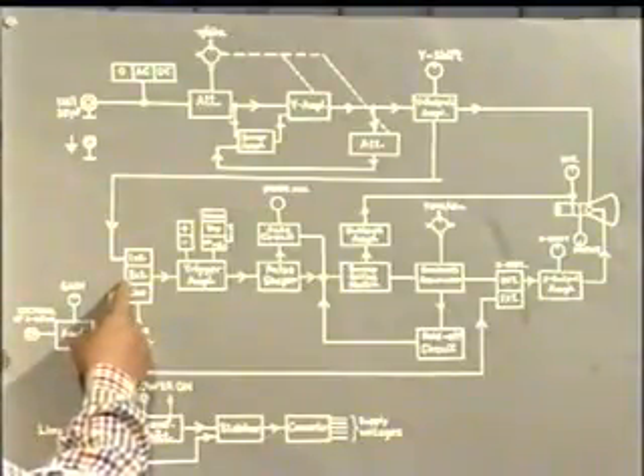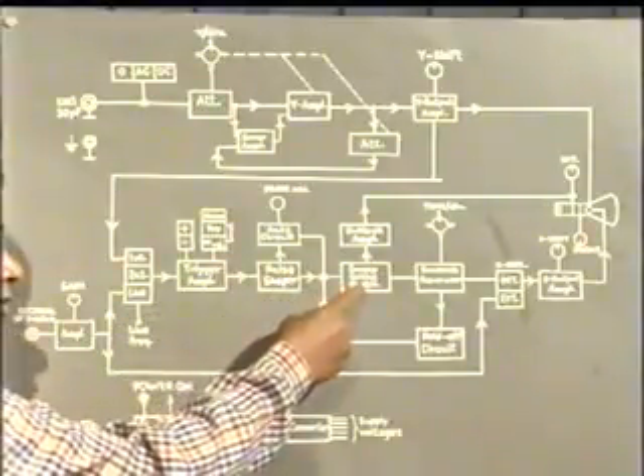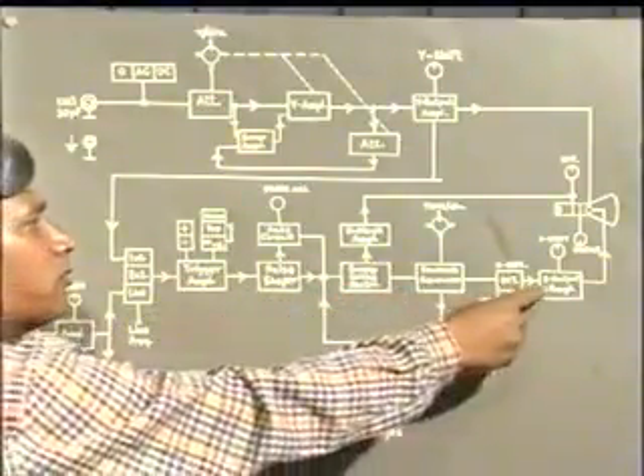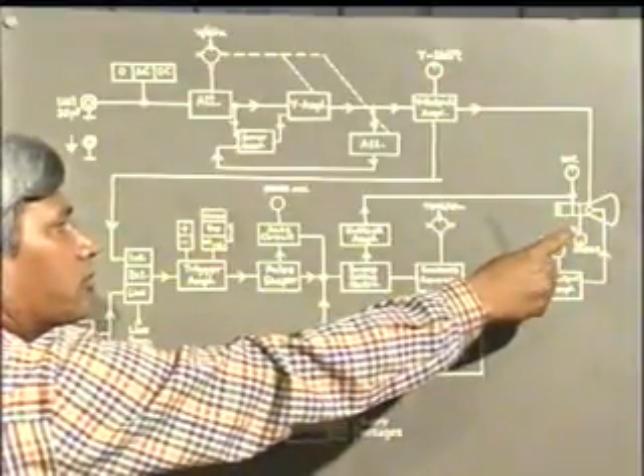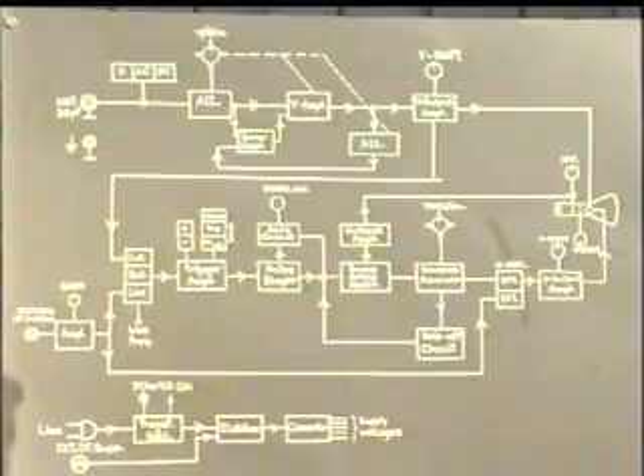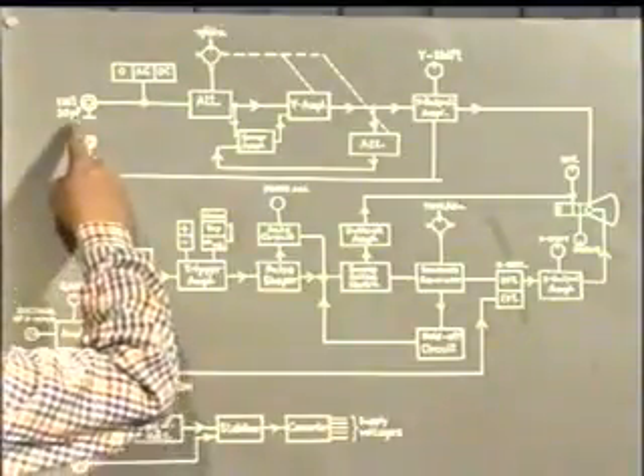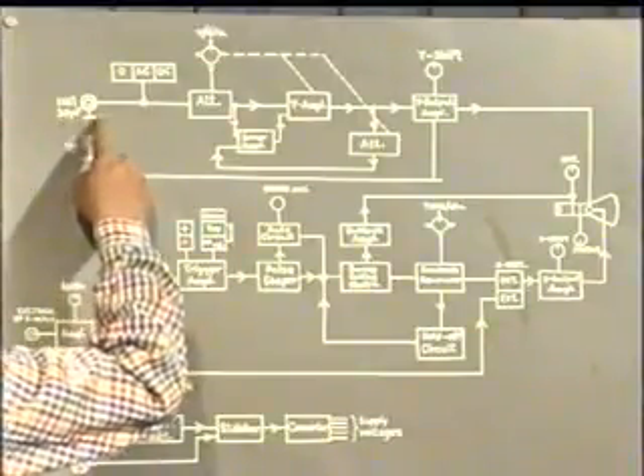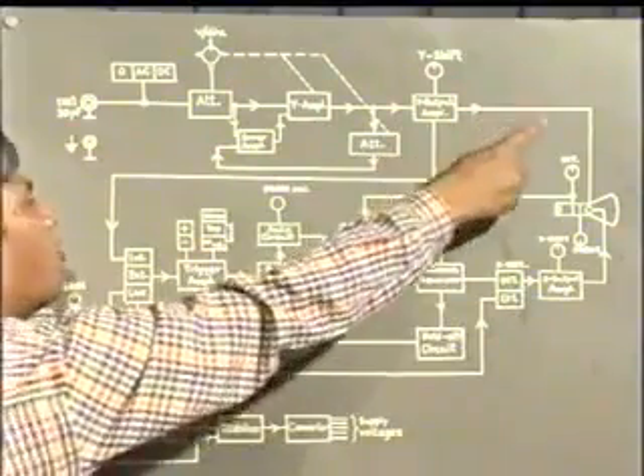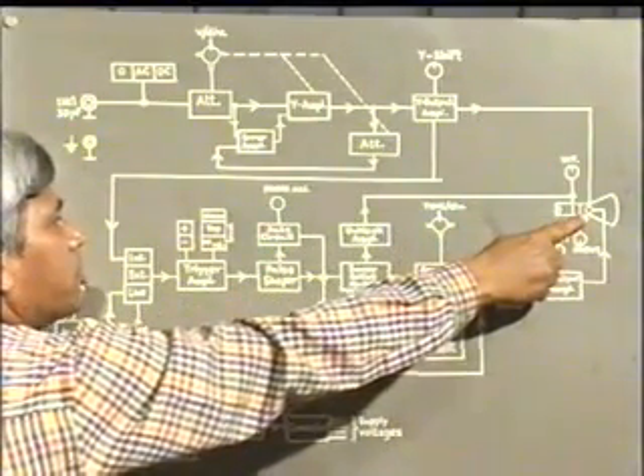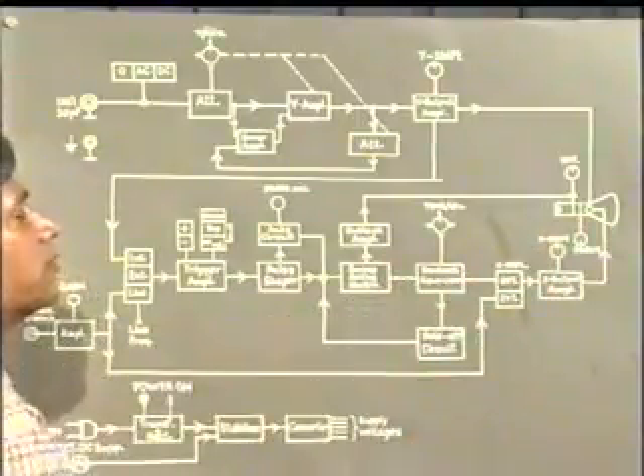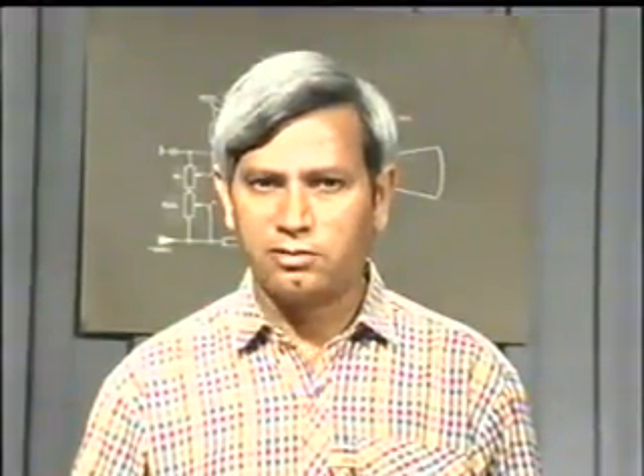The horizontal section generates the sawtooth and feeds it to the CRT to generate the beam, and the input to the CRO is fed to the vertical section that goes to the Y plates of the CRT to make the wave shape. To take up corrective maintenance, it is advised that one should first consult the service manual of the equipment.